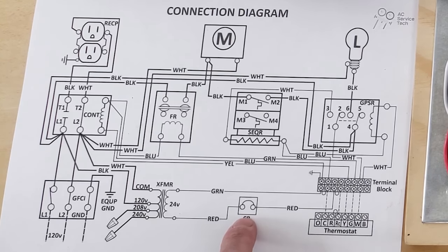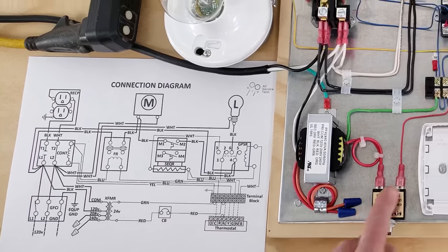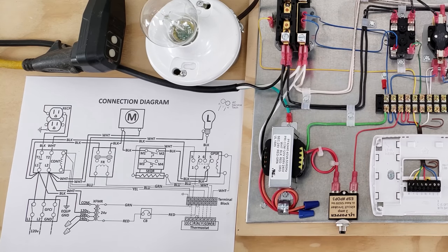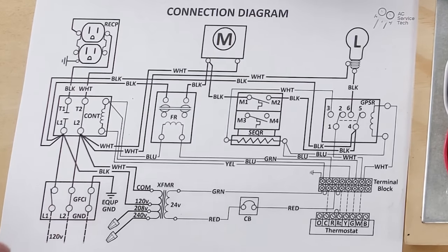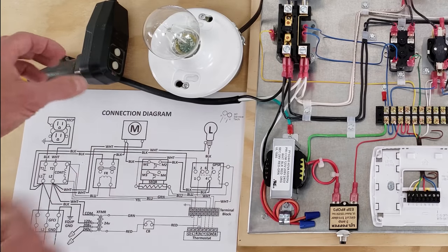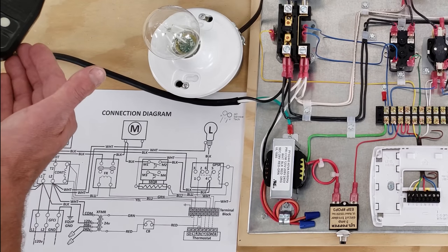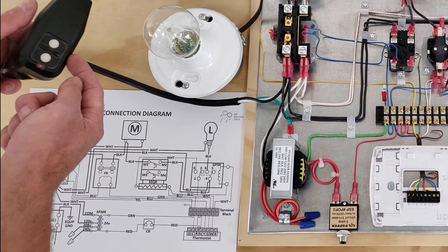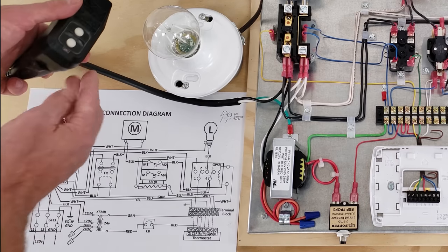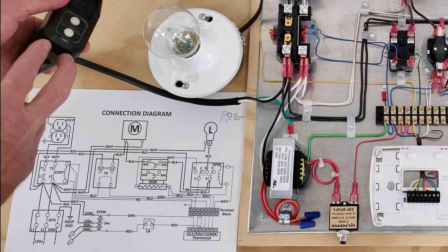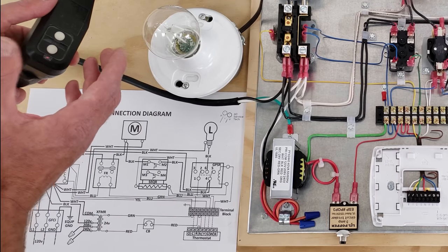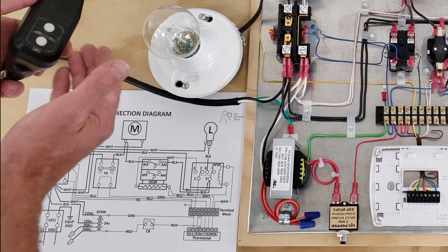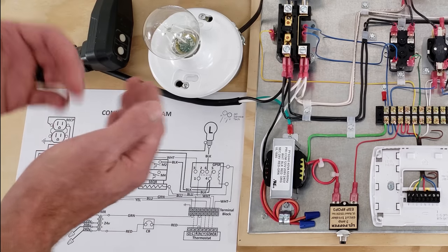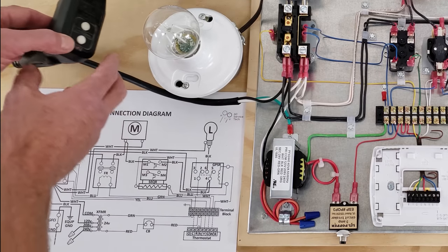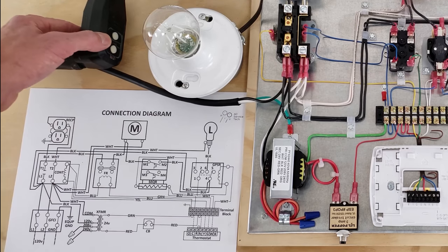So in this case, you see CB is right here, and that's connected to our red wire right here. So right here, we have a GFCI. This is very important for when your students are troubleshooting, you have a ground fault circuit interrupter. What this does is it monitors the current between the hot and the common. And if there's an imbalance, it's going to open up the electrical circuit as a safety, because that means that potentially there's current going through a ground, and that could be going through, say, your student, and that would be a danger. So that's why you have a ground fault circuit interrupter as your protection.